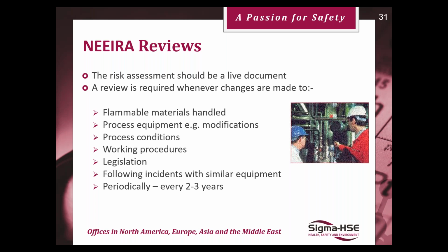And usually the NEEIRA is more specific, specific in the sense that your safeguards are specific just for your process. So when you buy ATEX rated equipment, the equipment could be rated for a range of use cases, whereas the NEEIRA is more specific. As I mentioned, when you write your safeguards in your tables, you might say, oh, my process is only run in batches, that this allows a degree of cooling, which is a safeguard against hot surfaces. So it's specific in that sense.